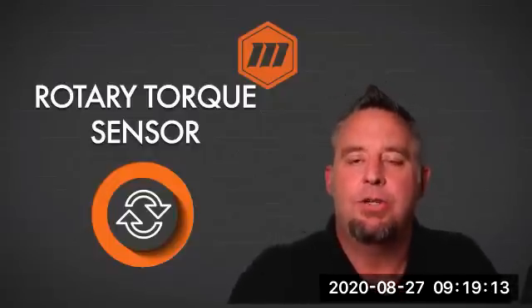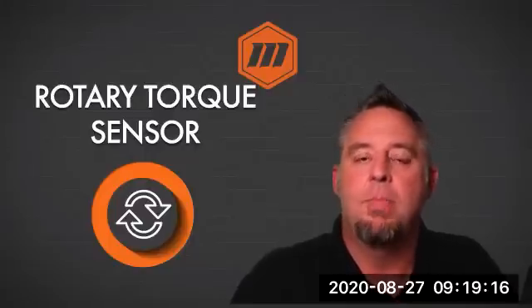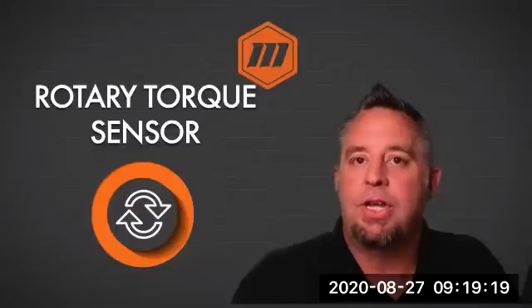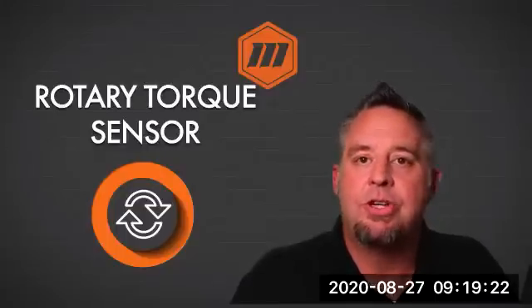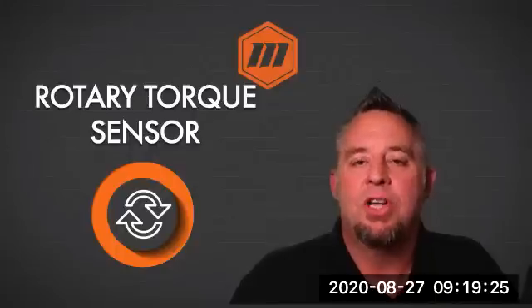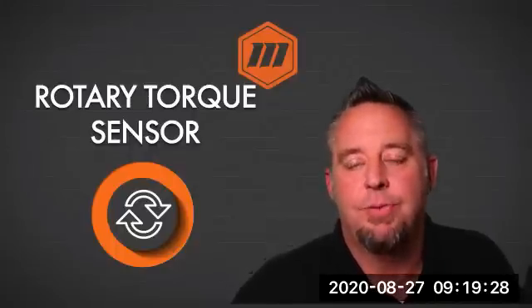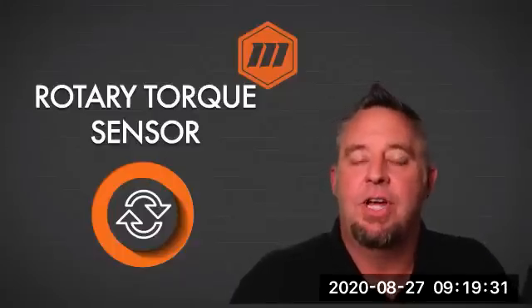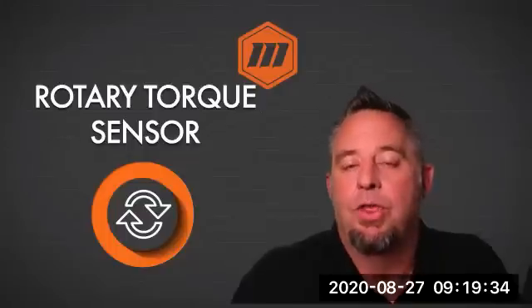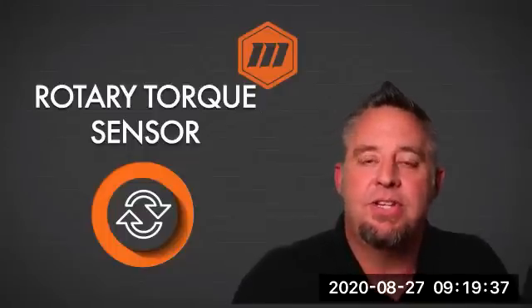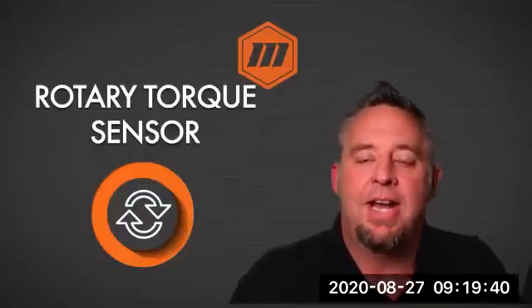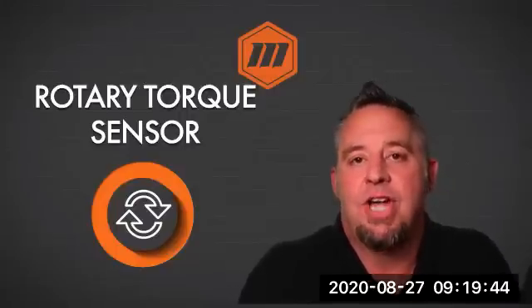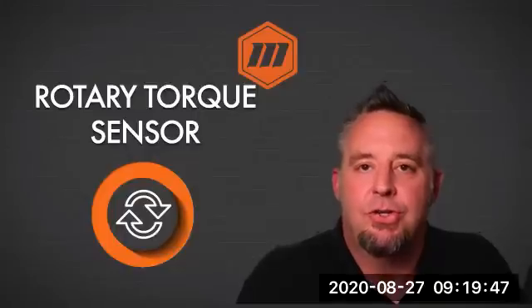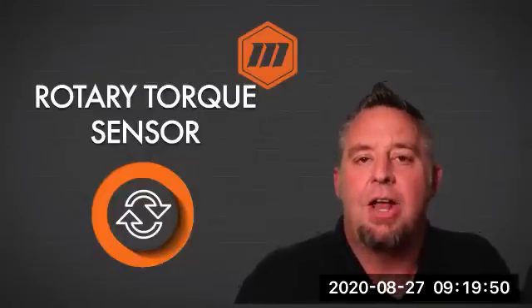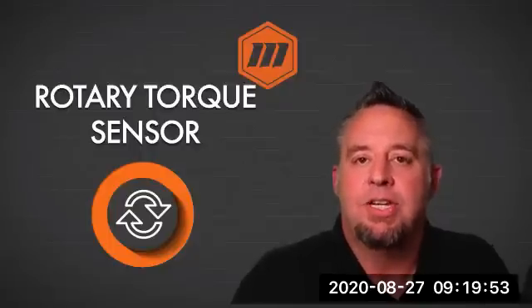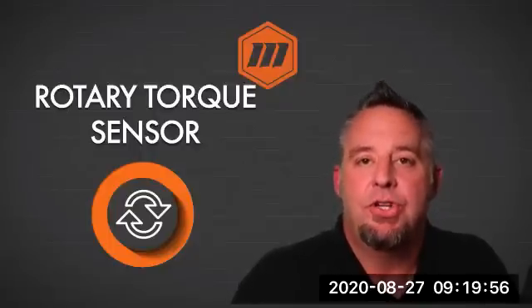Now, if we want to be able to constantly monitor our torque output during our assembly process, we can certainly use a rotary transducer to do that as well. But we would want to use a brushless rotary sensor, which allows us to have a maintenance-free process with no contact on the moving pieces—that's all done through magnetics. We also have that same brushless style available in an angle transducer, giving you the ability to continuously monitor your application if you so desire.